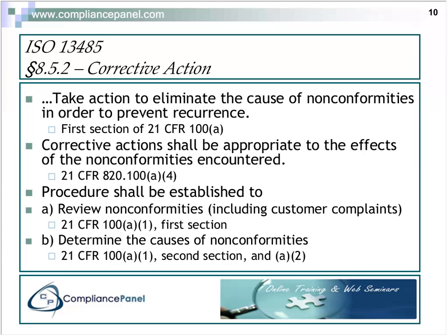This is another reason why I encourage people to lean towards the FDA regulations. It's easier to know what the requirement is when your actions have to be validated, they have to eliminate the nonconformity, and they can't adversely affect your device. Those are three things you can digest easily. The word appropriate is completely open to interpretation until, of course, your notified body comes in, does an audit, and cites you for non-appropriateness.